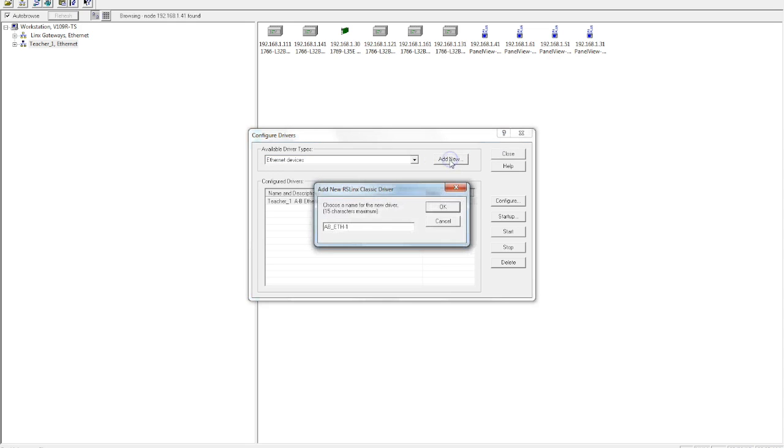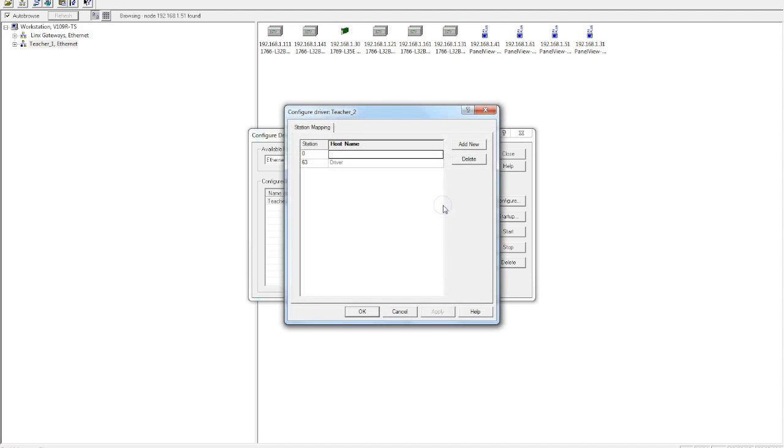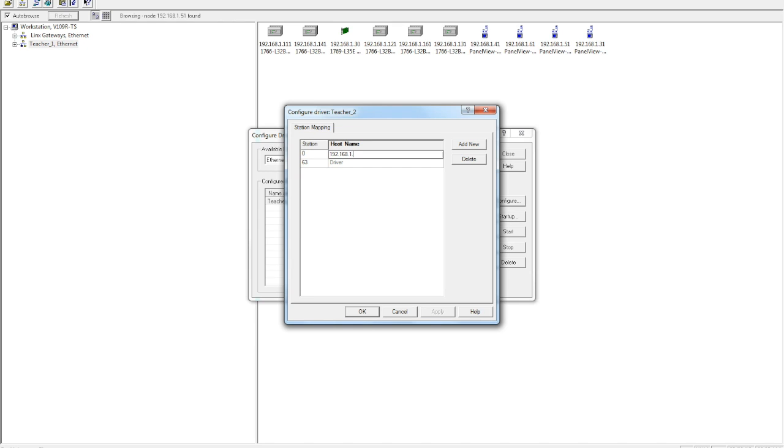I select Add New again. This time, I'll give it a different name. I like to specify my drivers, just in case there's multiple drivers on my RSLinx. It really helps me to keep everything organized. So I'll identify this as Teacher 2. I'm going to select OK. Now this one's going to ask you for a specific IP address, the IP address that is specific for the PLC that you're using. So the IP address that I'm going to go for right now is 192.168.1.111.